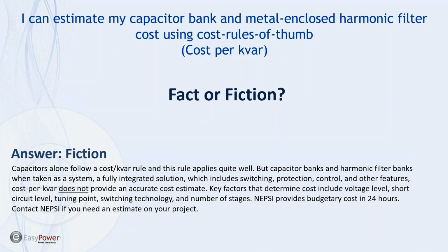There's also the voltage level, whether it's a filter bank or a capacitor bank, and how many kVAR per stage. These are all factors that come into the cost of a filter bank or a capacitor bank. The cost per kVAR rule just does not work. What we tell our customers is, if you need a quote and you need it quick, just call NEPSI. We'll give you that quote within 24 hours. Budgetary numbers can often be given within a couple of hours. So instead of trying to use a cost per kVAR rule, just give us a call. We'll give you a strong budgetary number to work with.